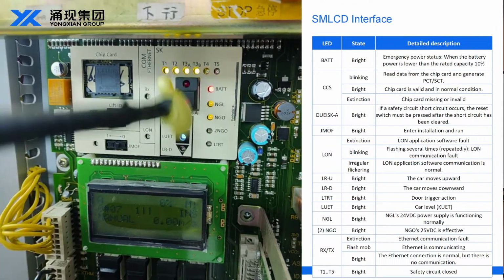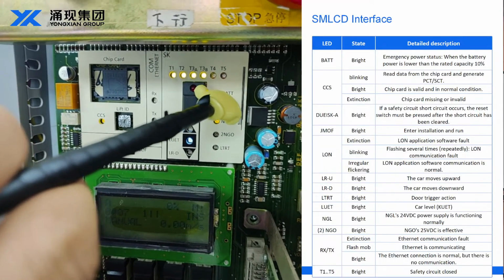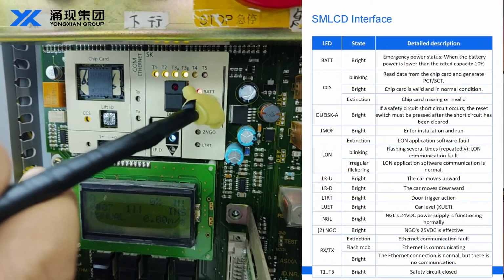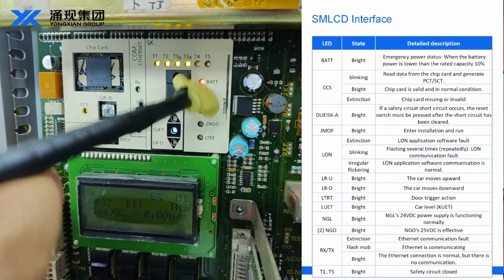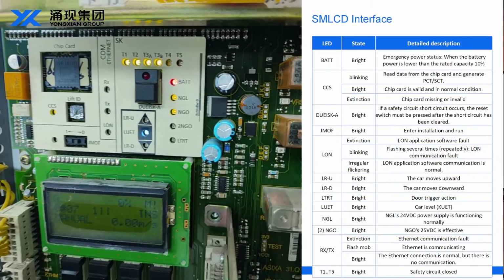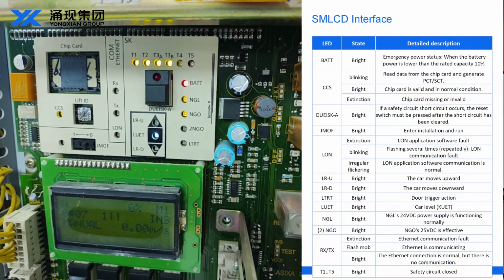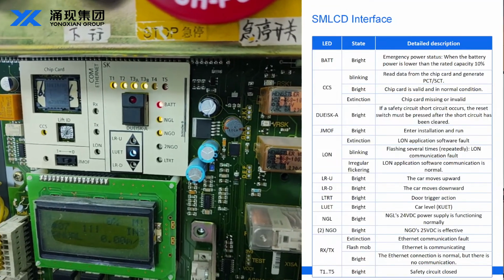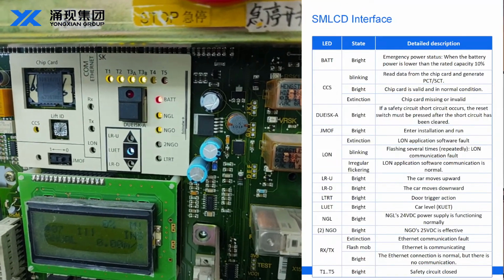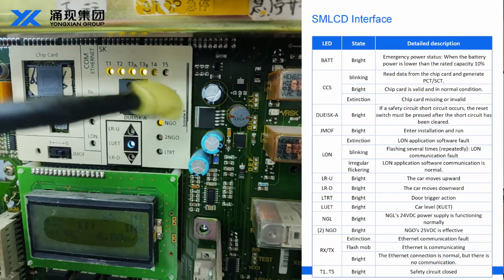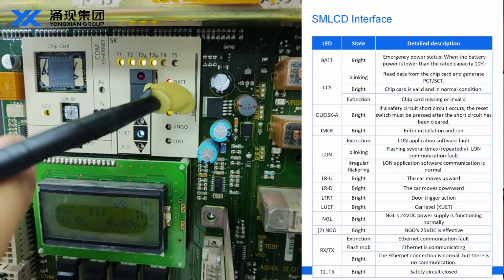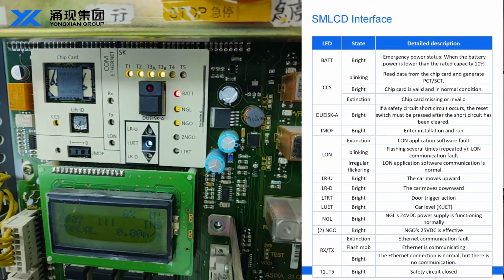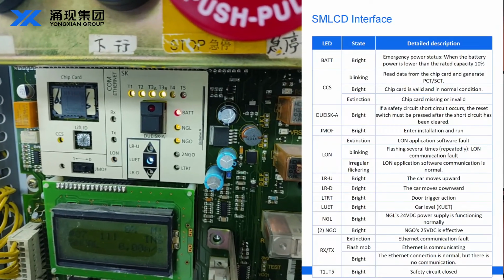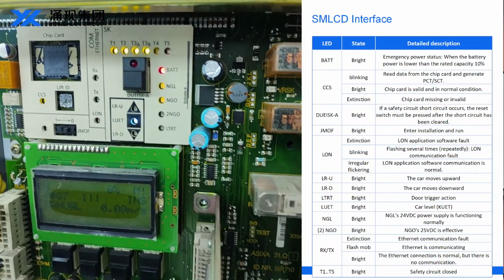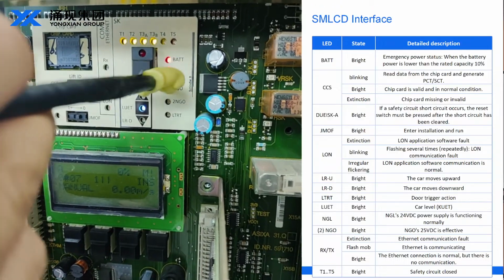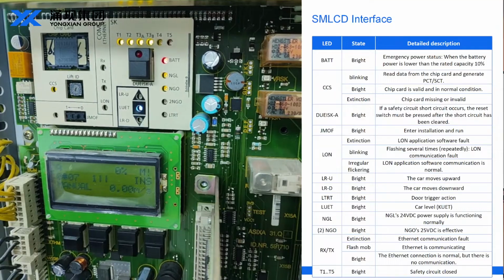Then let's first explain this part in detail, the battery, the emergency power battery, because we have not connected emergency power here. First of all is the battery light. It means when the emergency battery is good, the battery light will be on. Because this elevator doesn't have emergency power, this light is red, and normally it should be green. Next is the NGL, which means the 24 volt power is valid. The NGL, as you can see, the LED is green.